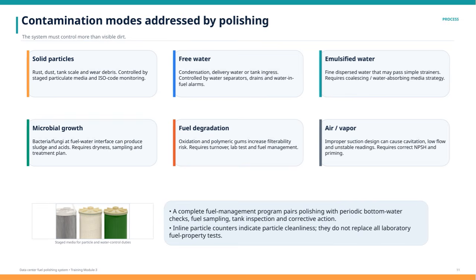First, we have solid particles such as rust, dust, tank scale, and wear debris. These are managed using staged particulate media combined with ISO code monitoring, which helps maintain cleanliness standards. Next is free water, which can come from condensation, delivery water, or tank ingress. This type of water is controlled by water separators, drains, and water-in-fuel alarms to prevent damage.